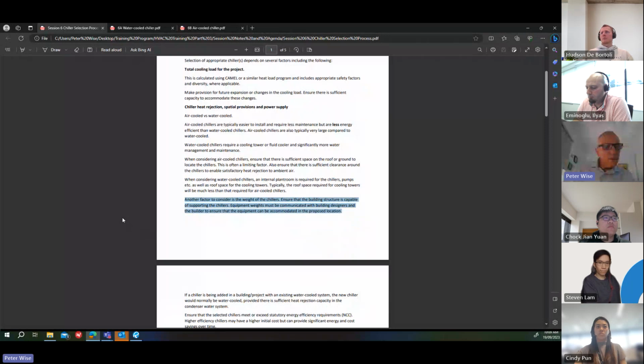Like a long time ago, actually about 40 years ago, in fact, I worked on a big project, a hotel project with casino, convention centre and so on. We had 4 quite large centrifugal water-cooled chillers in a plant room. And the plant room floor was actually suspended. And somewhere along the line, the communication must have failed, or the structural strength wasn't provided that it should have been. And the floor actually collapsed.